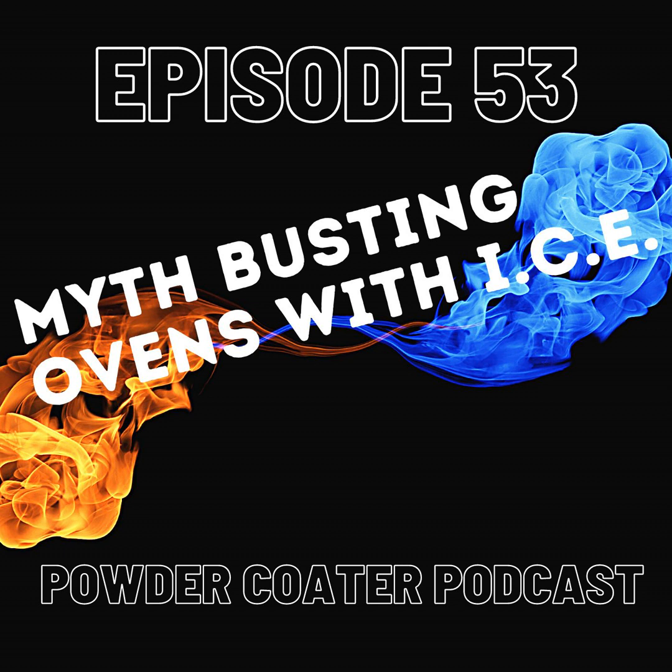How do you build an oven for such variety? Well, the key is you have to have good air movement. You have to have adjustability of your nozzles so you don't have any hot and cold spots, things like that. And we've played with different turnover rates over the years, especially on a gas type oven. We've settled in around 3 to 4 air changes a minute based on the volume. Seems to be about right.